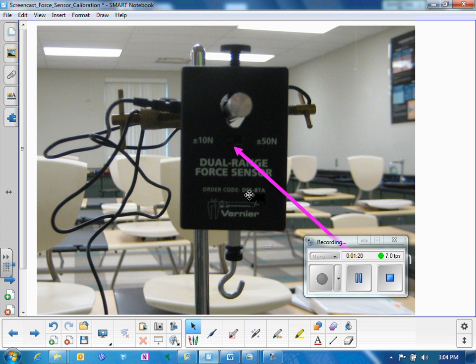You'll notice that it's called a dual range force sensor. That means it has one range between plus and minus 10 newtons and the other between plus and minus 50 newtons. For most of our work, we'll be using the plus and minus 10 newton scale. That means that we should not apply forces larger than 10 newtons. So be sure that the switch is moved to the left and that we're all set up for calibrating at plus or minus 10 newtons.